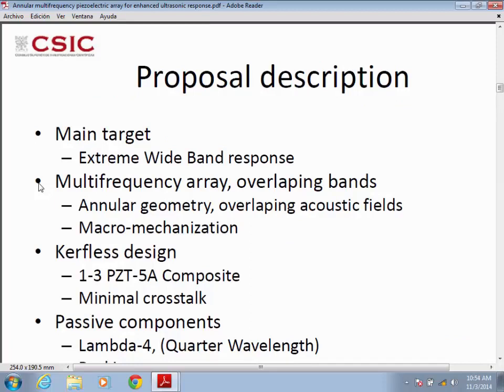We would like to design an array which has overlapping bands of frequency, and we chose an annular geometry with a two-element array with an outer ring and an inner disk, but using a machining process. We start with a ceramic, and instead of creating elements with the kerfing technology, we're using a composite which has a very low crosstalk between elements. So we machine this. In this case, we're using a 1-3 PZT-5A composite, and then we add different kinds of passive components to enhance this broadband response even further.